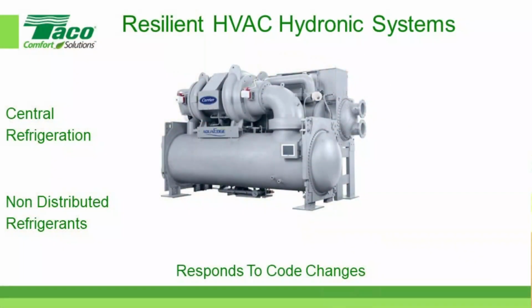And someone asked me, well, what about a water source heat pump? That's kind of a hydronic system, and I will show you one of those. Doesn't that have distributed refrigeration? Well, it has refrigeration at each terminal unit, but that refrigeration isn't tied to all the terminal units. So if you had a leak in one unit, all the refrigerant in the entire system doesn't leak out. It's unique to that one particular unit. Okay? So it responds very well to code changes. As the law changes, hydronic systems are resilient to code changes.